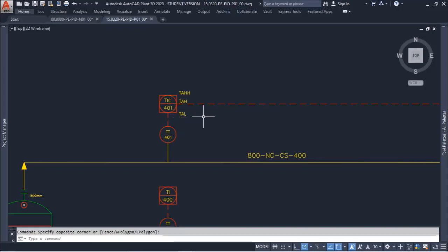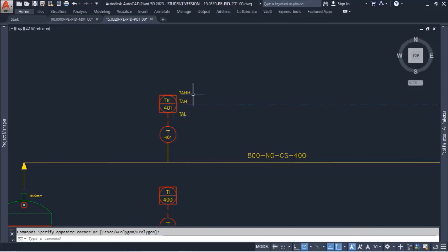for Alarm and for Shutdown. Usually when we have only one letter, it is for Alarm. When we have two of the same letters, it is for Shutdown.